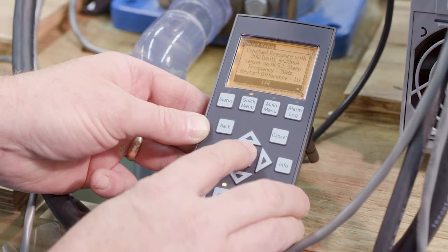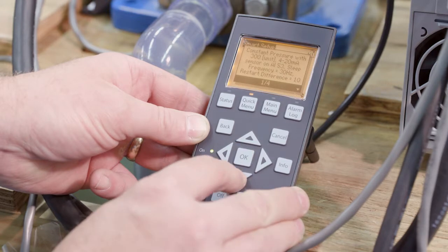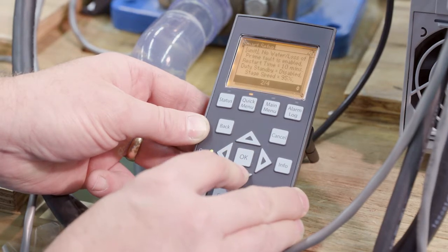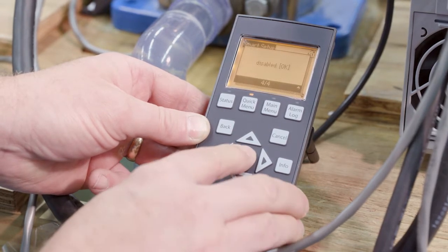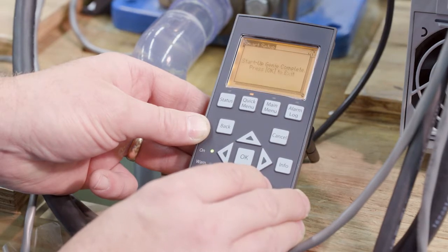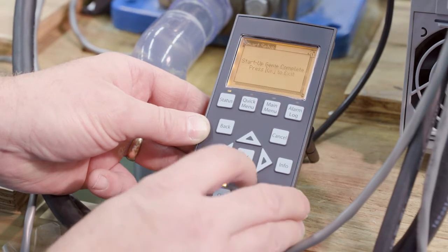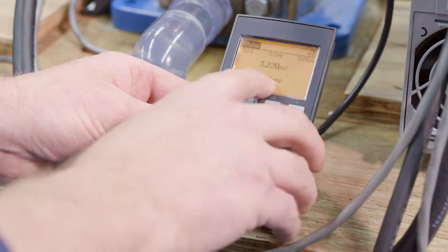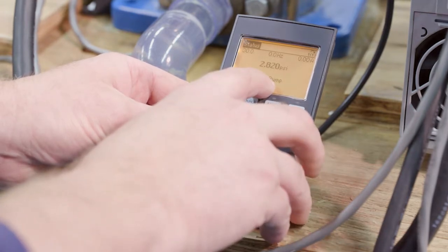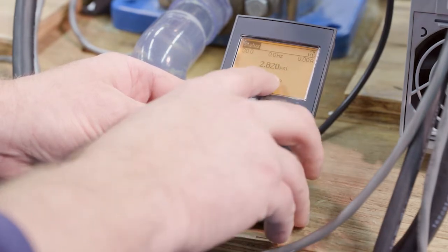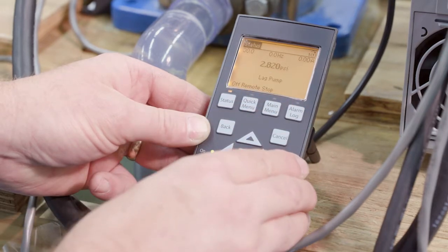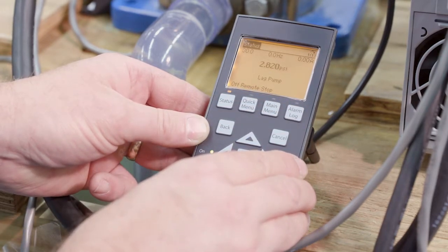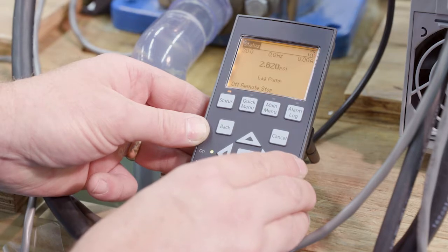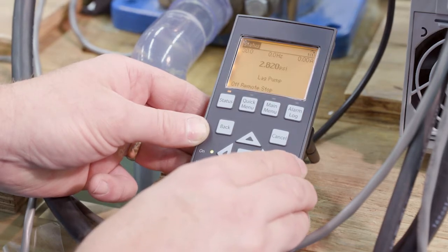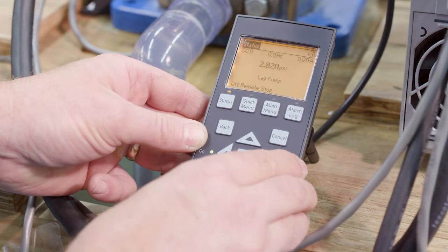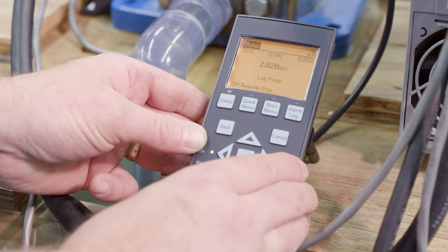Okay, again, reminders of your auto set. So we'll scroll through those. Hit OK. Startup Genie complete. And notice that we have lag pump here, in system pressure, lag pump. And so now our wiring is complete and our programming is complete for a multi-master, multi-control duplex system.